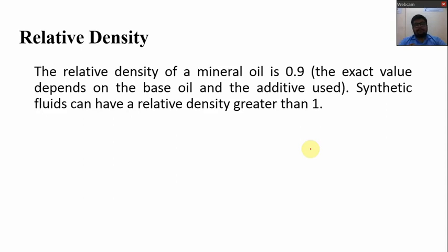The next is the relative density. The relative density of a mineral oil is 0.9. The exact value depends on the base oil and the additives used. Synthetic fluids can have relative density greater than 1. So the relative density is important when designing the layout of the pumps and the reservoirs.